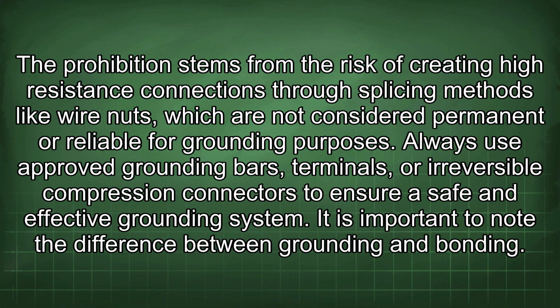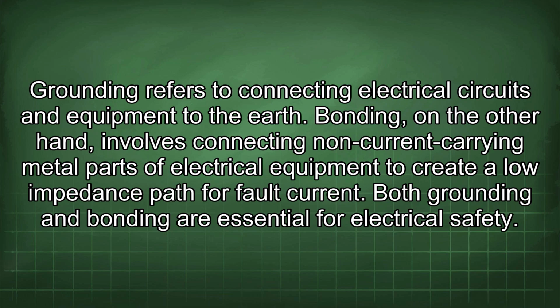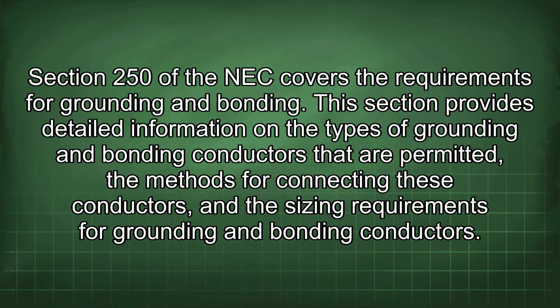It is important to note the difference between grounding and bonding. Grounding refers to connecting electrical circuits and equipment to the earth. Bonding, on the other hand, involves connecting non-current carrying metal parts of electrical equipment to create a low impedance path for fault current. Both grounding and bonding are essential for electrical safety. Section 250 of the NEC covers the requirements for grounding and bonding. This section provides detailed information on the types of grounding and bonding conductors that are permitted, the methods for connecting these conductors, and the sizing requirements for grounding and bonding conductors.